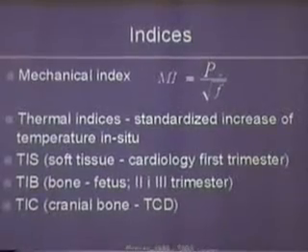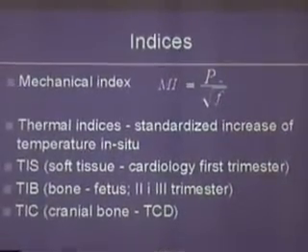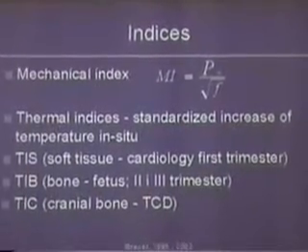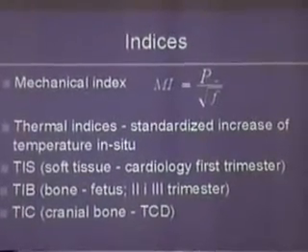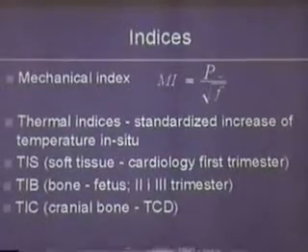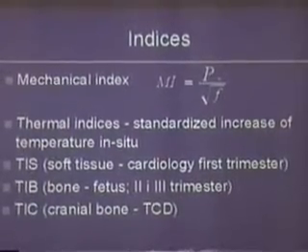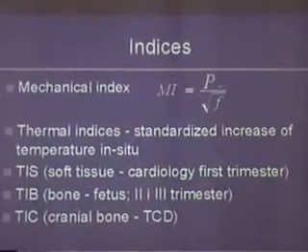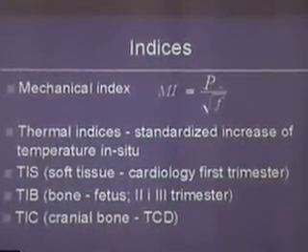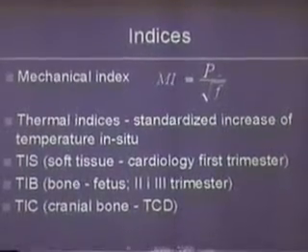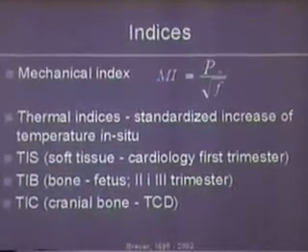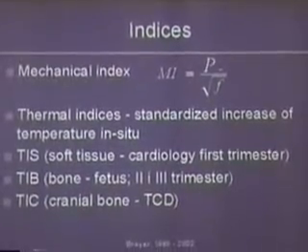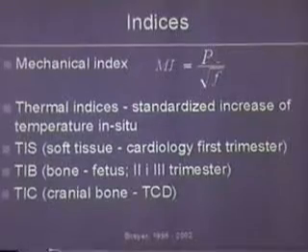Although it's a gross idealization, you ought to know that the number you get there, like 1.3 or something like that, really means a theoretically calculated increase of temperature in degrees Celsius in situ. That's in the patient that you are just scanning.